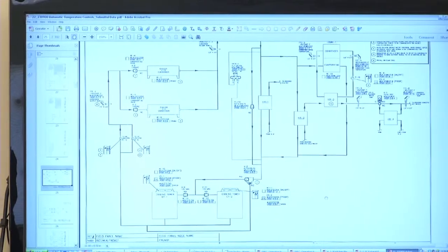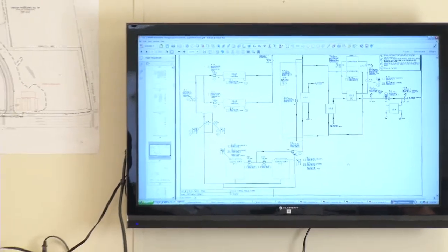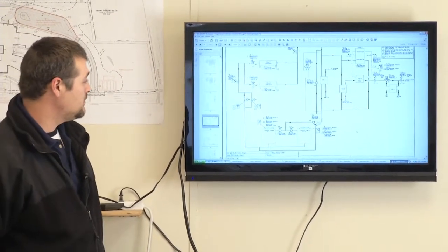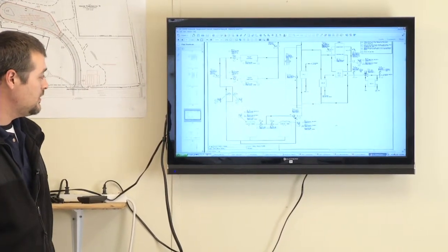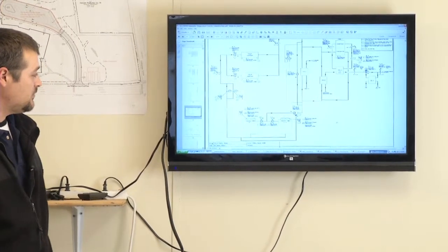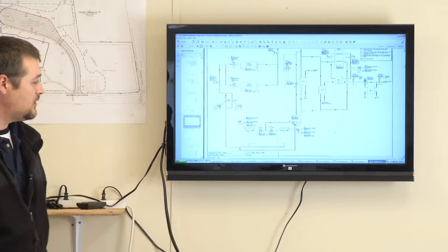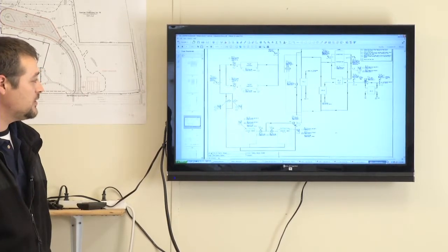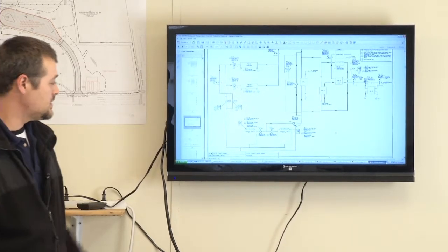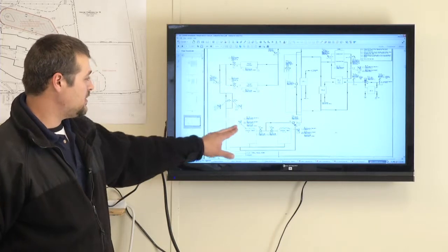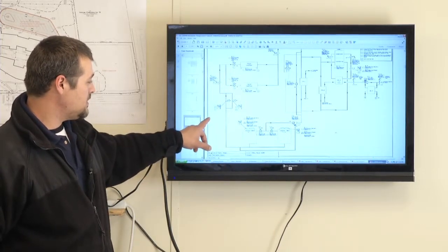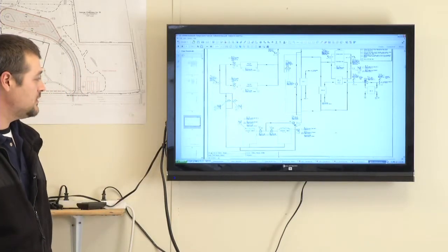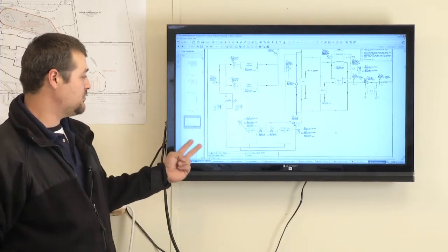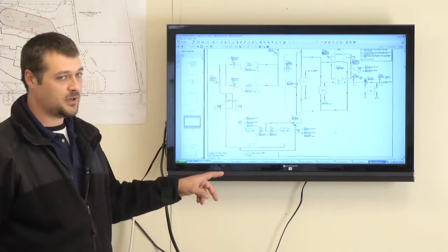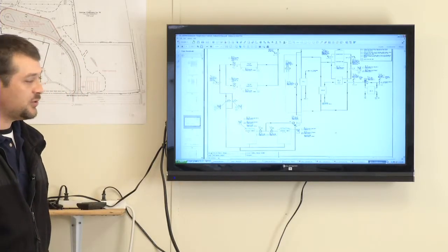Now we're going to discuss some of the features you'll see on the graphics of this screen. This screenshot is in the submittal and the OEM package, but it also may resemble what you find on the graphics of the operator. In the case of an alarm generated from a pump or cooling tower fan, you would have a red point in place of the text that's black here, and you'll also have an alarm screen at the bottom of the toolbar that would flash, letting the operator know that there's an issue with a piece of equipment. In the case of one of these cooling towers alarming or one of these pumps alarming, the text would be red around the point indication, and you would also see the secondary point energized. Whenever we have an alarm and there's two possible pieces of equipment to run, then we switch over and we'll operate the lag equipment or whatever point is available.